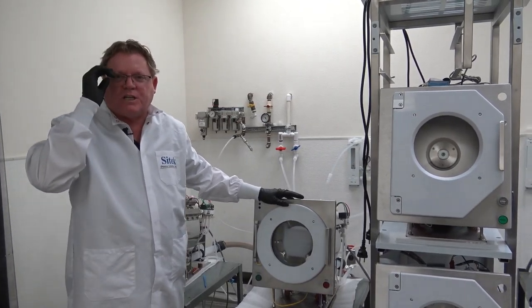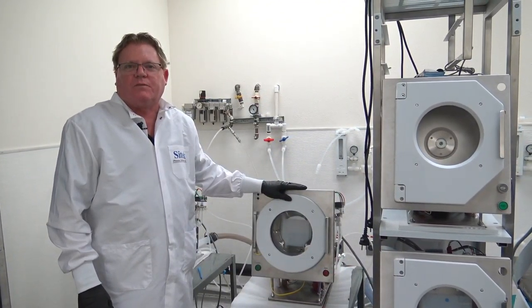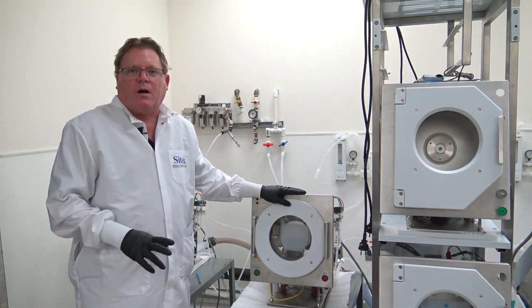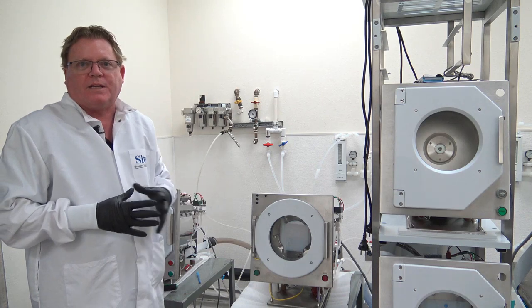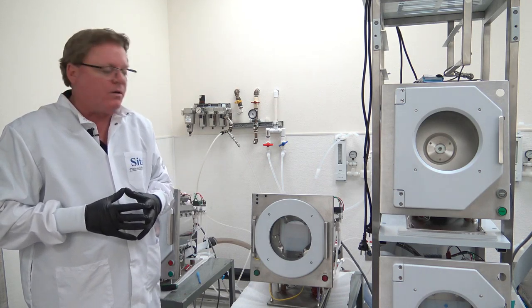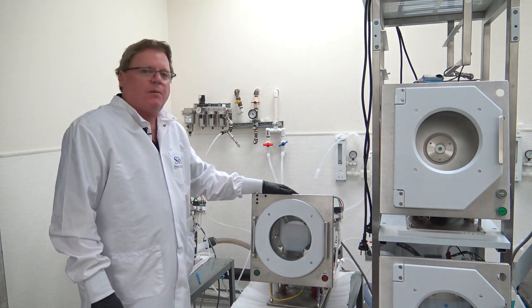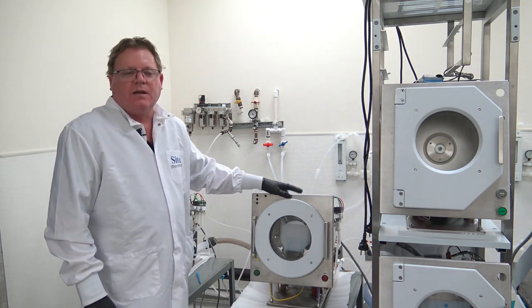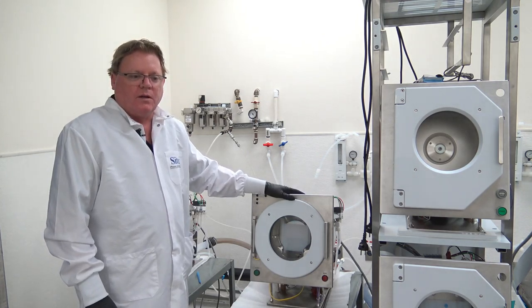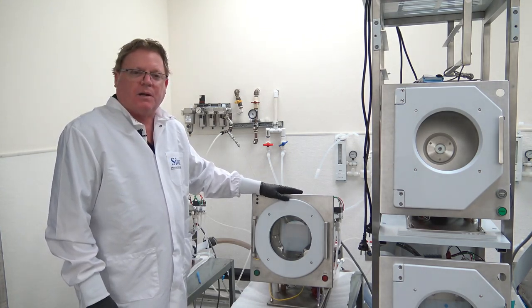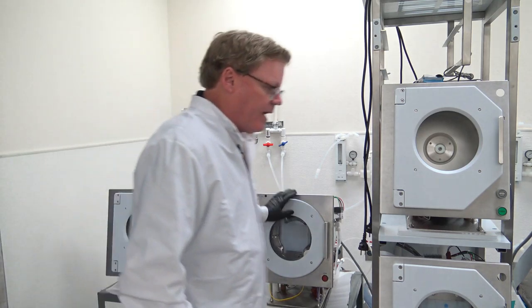This was a traditional ST unit. We were able, the customer wanted to upgrade the technology of the controller. So our new SciTech state-of-the-art touchscreen controller never worked with the STs. It used the F and the S model. We've upgraded this ST to have the correct parts needed to run like an F model. And the customer purchased our new state-of-the-art controller and upgraded their tool. And this will be the first tool ever that's been upgraded from an ST to the SciTech state-of-the-art controller for reference. We're really happy about that.